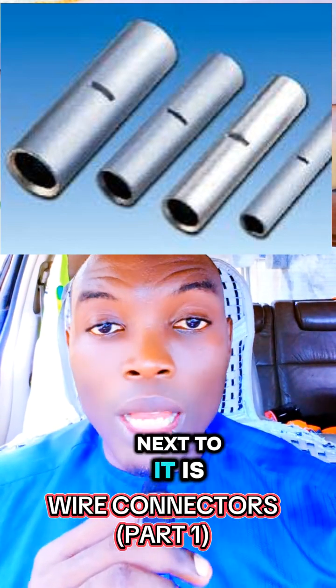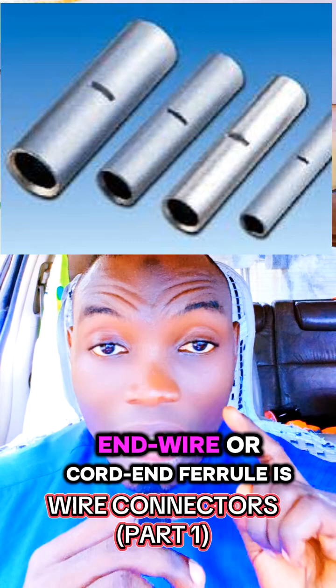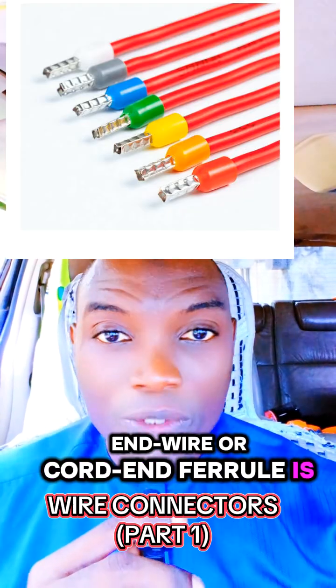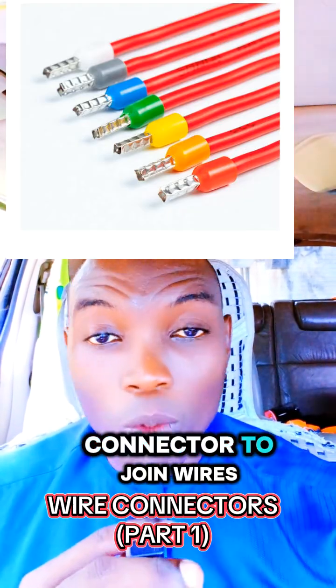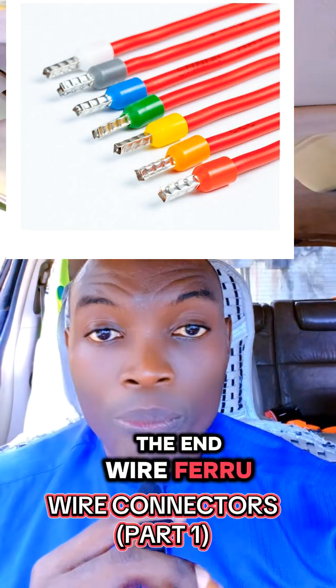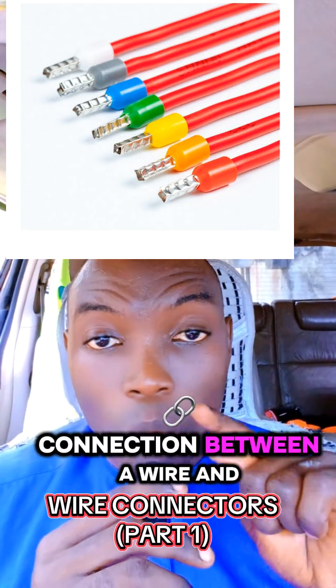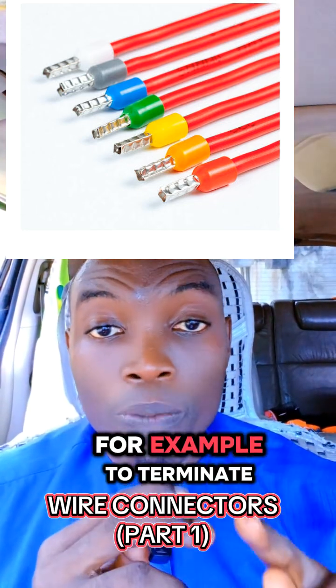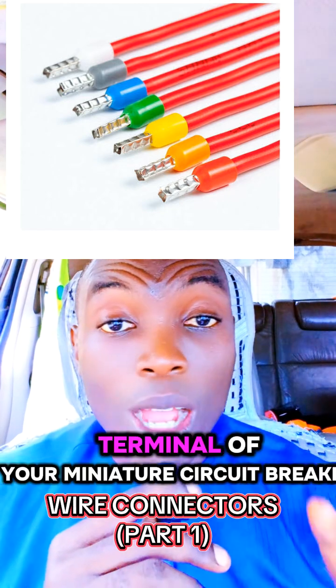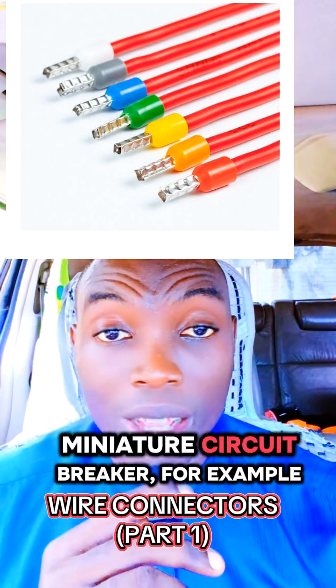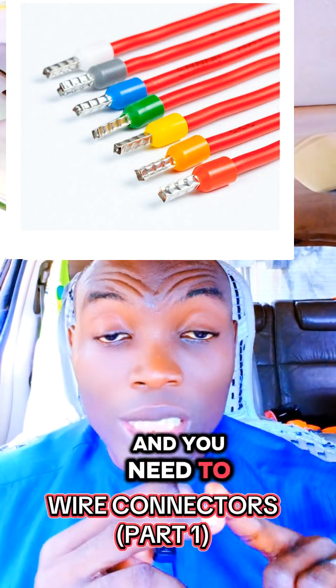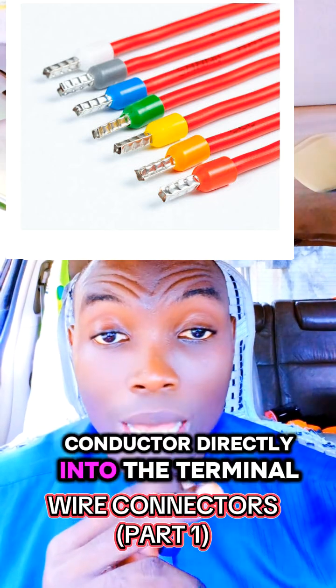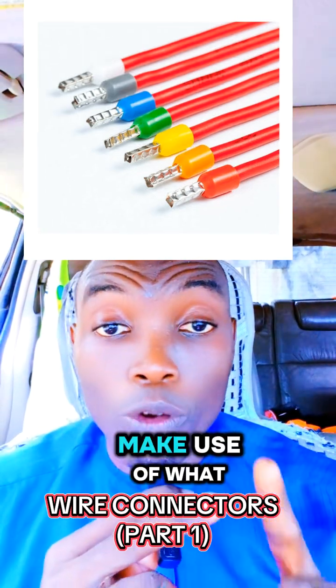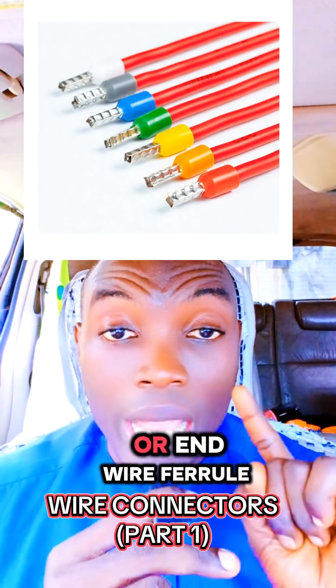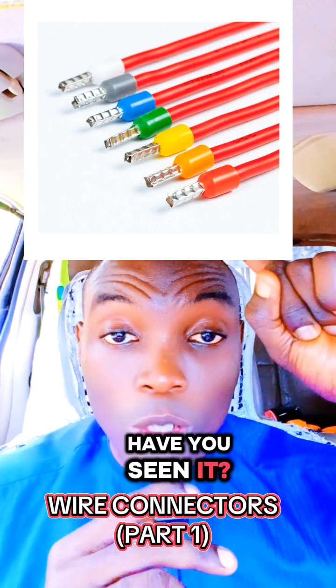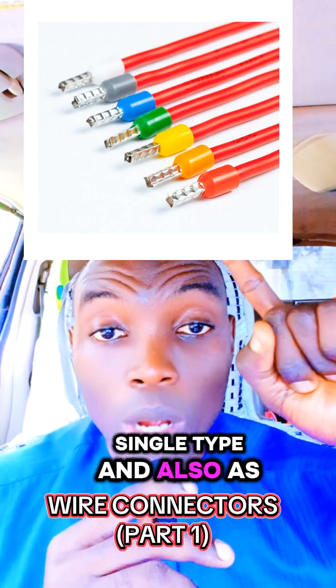Next to it is the end wire or cord end ferrule. It's also a ferrule. We use it as a connector to join wires, but the end wire ferrule is used to provide connection between a wire and a terminal. For example, you want to terminate your wire to the terminal of a circuit breaker, a miniature circuit breaker. Instead of inserting the conductor directly into the terminal, you are supposed to make use of what you call a cord end or end wire ferrule. Have you seen it? It comes as a single type and also as a multiple.